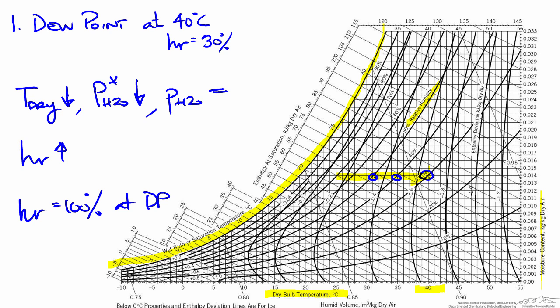Continuing left all the way to the 100% saturation curve, we find the dew point. The temperature can be found along the saturation curve. Here is 20 degrees — we are a little bit less than that, so we are slightly over 19 degrees. We can also confirm this by dropping straight down to the x-axis, and again we can see that our temperature is slightly over 19. So in this case our dew point is about 19 degrees.